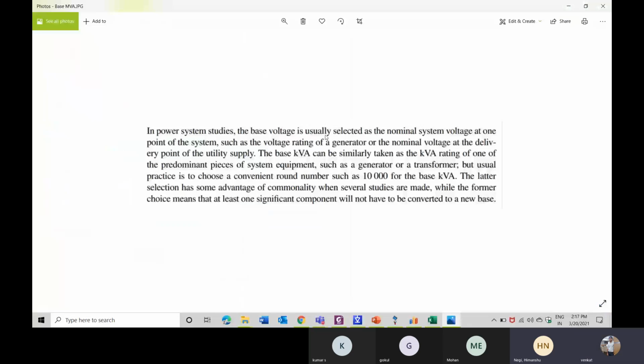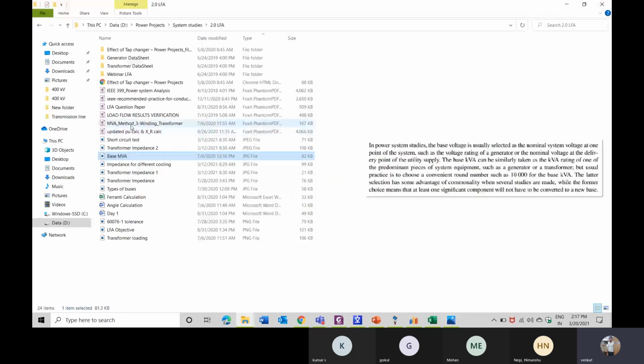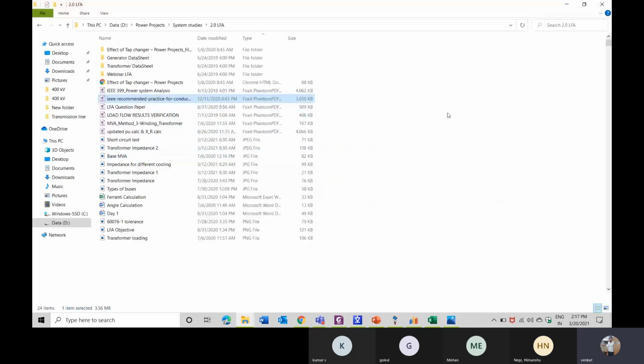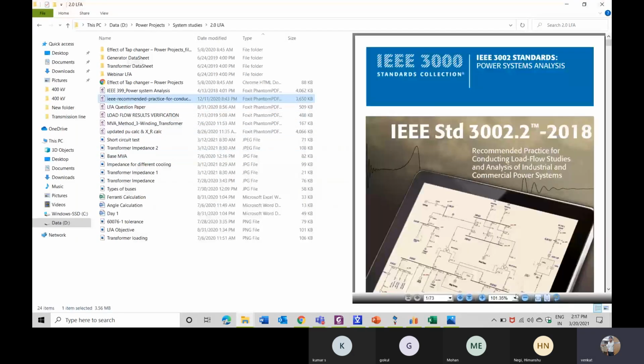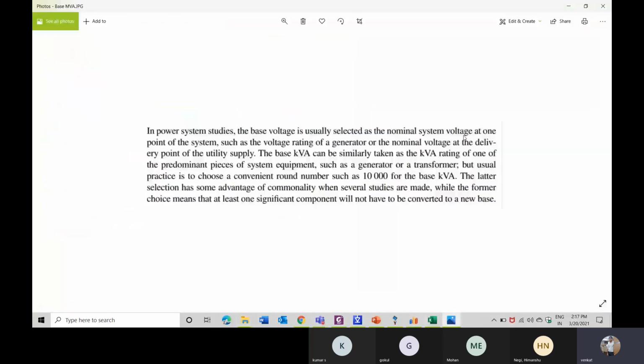Here you can see this - this is a snapshot from the standard called IEEE Standard 3002 series, for load flow. This is the series we used to take for load flow, IEEE Standard 3002.2. From that I have taken a snapshot showing how to choose the base MVA.